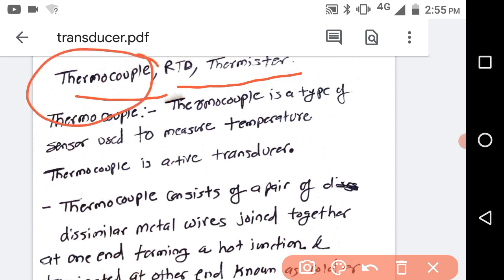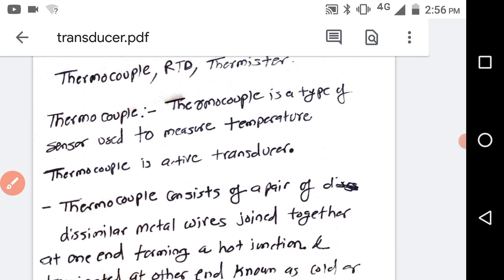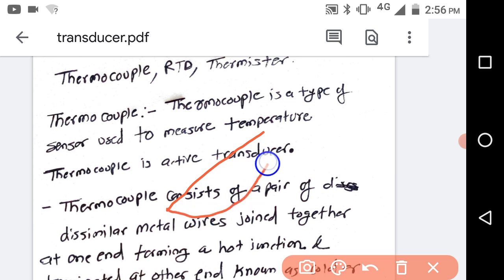Thermocouple doesn't need any external supply for its conversion of temperature to the electrical energy. RTD and thermistor require the external voltage supply, so they are passive. So what is thermocouple? So when two metal wires of different temperature are joined together, so two metal wires when they are connected together, and suppose one junction is subjected to the high temperature or heat, then its temperature will be high in comparison with the other junction. And whenever there is a temperature difference, EMF is induced between these two junctions.